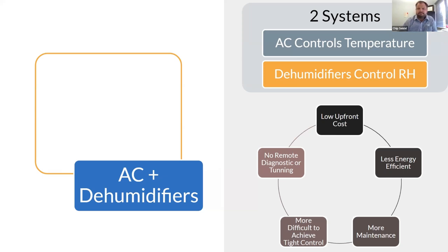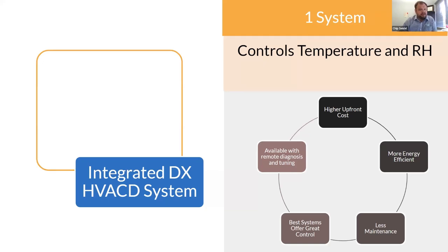The next system is the integrated direct expansion HVACD system—D stands for dehumidification. This gives you a higher upfront cost but much more energy efficiency, significantly less maintenance, and really good controllability because you've got that variable sensible heat ratio. You're able to throttle on and off dehumidification, cooling, and heating to get right where you need to be. These systems aren't all created equally, but they're available with remote diagnostic and tuning abilities, especially the purpose-built systems for indoor agriculture. You're able to view all aspects of the system remotely, and the factory can as well—so if there are any issues, they can zoom in, take a look, make adjustments, and provide support.